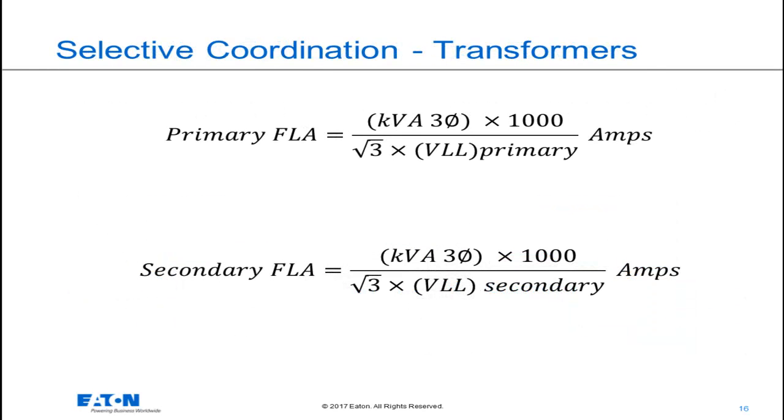These are the two important equations you need to know. The basic difference between these two equations is that the primary full load amps is based on the line-to-line voltage on the primary, and the secondary full load amps is based on the line-to-line voltage of the secondary.